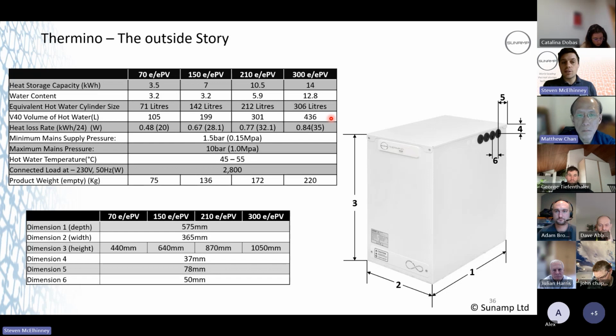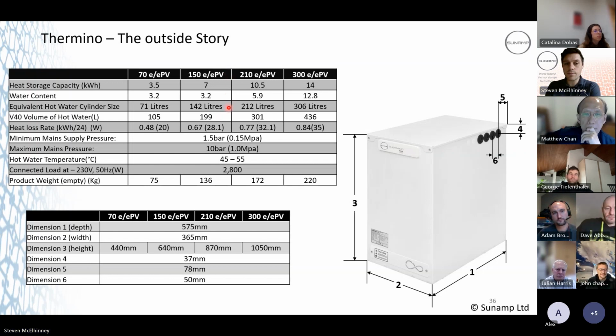This is based on a 10-degree inlet temperature from the street as well. So obviously, when we start going into the winter time, there's going to be a higher heat exchange going on, because the cold mains water temperature is lower. So this will be a little bit lower, but it gives you an idea of what the battery is capable of. I mean, we had a project in Guatemala, and they were fitting 150s, 150 EPVs. And their V40, they were telling us they were getting about 400 litres from that. They were doubling their V40 because their inlet temperature was 20 degrees from the street, so there was less of a heat exchange going on. So they increased their capacity massively.